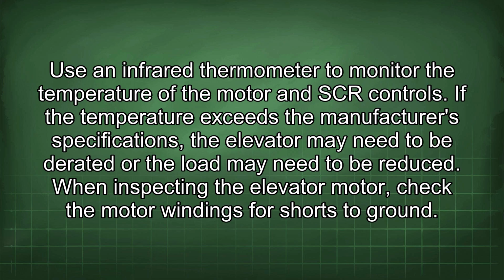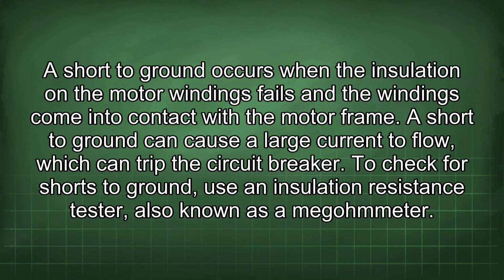When inspecting the elevator motor, check the motor windings for shorts to ground. A short to ground occurs when the insulation on the motor windings fails and the windings come into contact with the motor frame. A short to ground can cause a large current to flow, which can trip the circuit breaker.